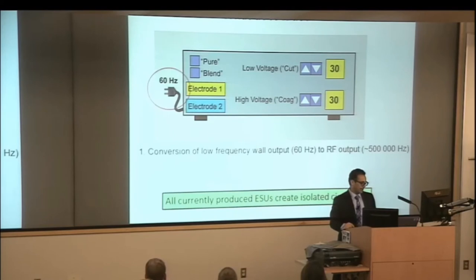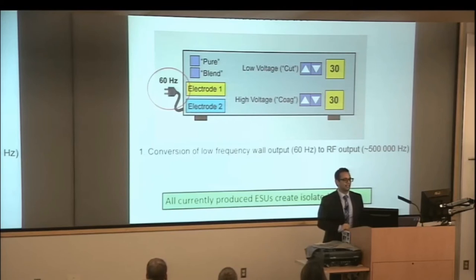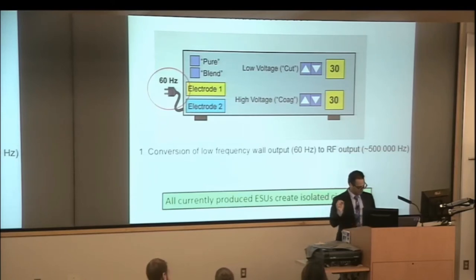First, it converts the frequency from the wall output of 60 hertz to over 100,000 hertz. The reason is, have you ever wondered why you don't electrocute your patients every time you use that? It's because that high frequency bypasses the nerves' and muscles' ability to depolarize, so you don't electrocute people when you use it. You also want that very high frequency because it causes the thermal effect you want when the ions move back and forth.